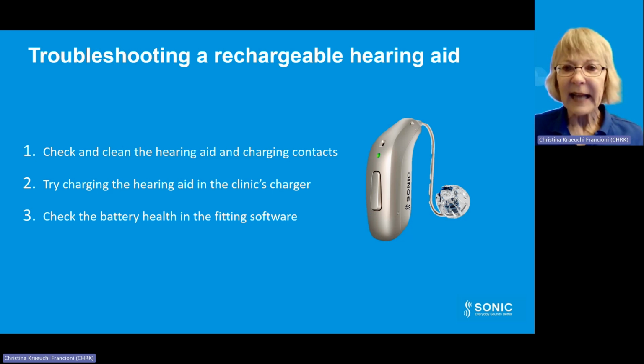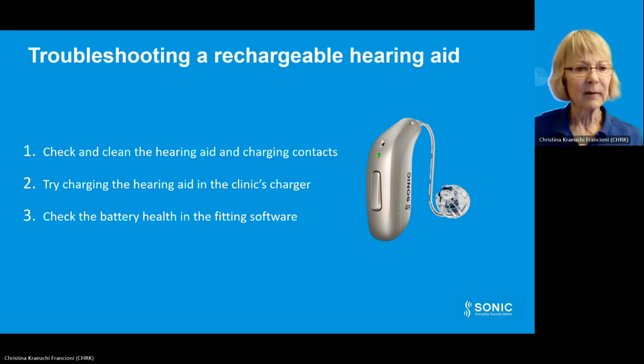To check if it's your client's hearing aid or the rechargeable battery in the hearing aid, please follow the next 3 simple steps. First, start by checking and cleaning the hearing aids as well as the charging contacts on the hearing aids. Second, once cleaned and the hearing aid works, which means it turns on and there is sound output from the receiver, try charging the client's hearing aids in the charger you have in your clinic. Third, once the hearing aids have been charged for approximately 15 minutes, you can check the health of the rechargeable hearing aid battery in the fitting software. Based on this information, you can see if the battery is the issue.